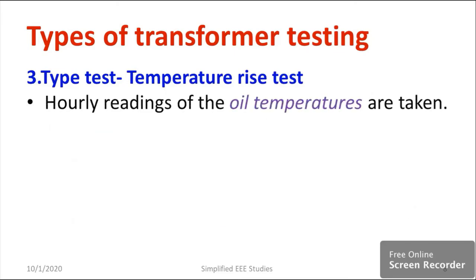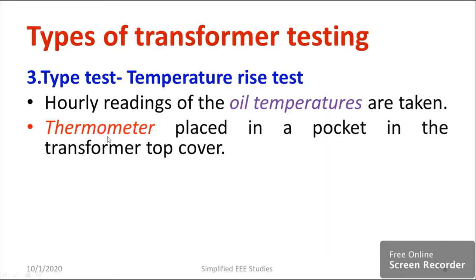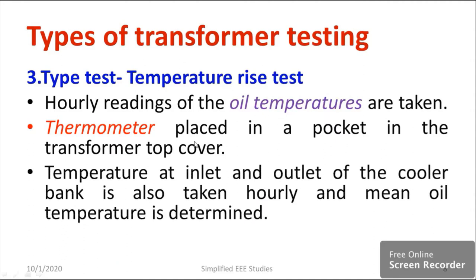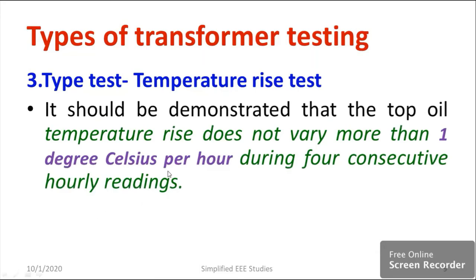We need to take hourly readings using a thermometer. The temperature at the inlet and outlet of the cooler bank is also taken per hour, and the mean oil temperature should be calculated. The ambient temperature — that is, the atmospheric temperature — has to be measured. We must ensure that every consecutive hour the temperature rise should not exceed one degree Celsius per hour.